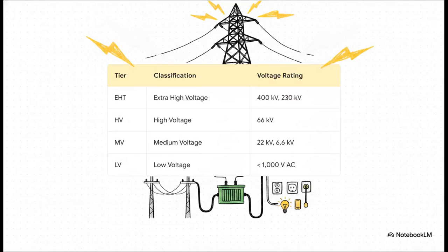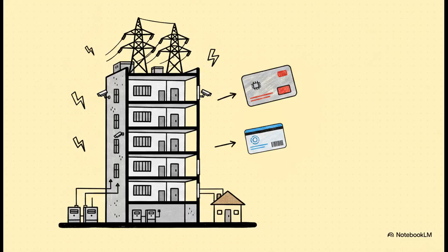So let's look at the actual rungs of this ladder. Up at the very top, we have extra high voltage, or EHT. That's your 400 and 230 kilovolts. Drop down a rung and you hit high voltage, or HV, strictly sitting at 66 kilovolts. Below that is medium voltage, MV, which covers 22 and 6.6 kilovolts. And finally at the base, we have low voltage, LV. That's the stuff coming right out of your wall socket, 400 volts three-phase and 230 volt single-phase, basically anything below 1,000 volts AC.